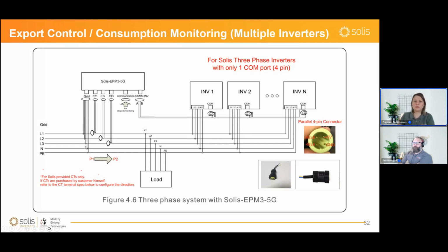It will take its power supply from the AC side. And if it's a Solis EPM3-5G, for now you will need 3-phase power supply. So you can't just start it with 1 phase, you will need all of them. So the grid port, where you will connect the 3 phases. Excuse me, my voice needs a bit of refresh. So this grid port, where you would connect the 3 phases, it will take its voltage measurement from here. And also you have the CT ports where you connect each of the CT clamps. If we're talking about EPM 3-phase, then it has the communication port where you would connect a data logger to it, and the COM-INV port where you connect the inverters in parallel.